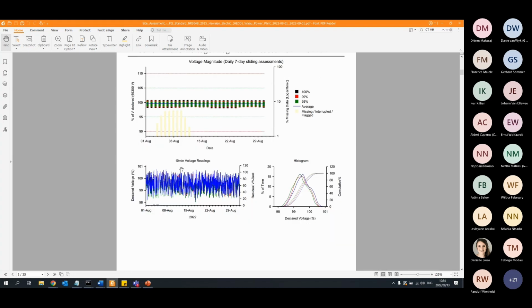So that's all well. If you look at the 10-minute readings, the actual readings and not the sliding assessment, you can see how your three phases change over time. And this is most likely impacted by daily loads that go up and down. If you look at the histogram, we can also see it's well balanced. So your three phases are well balanced. And for most of the time, the highest peak, 15% of the time, it's close to 99.5% of the declared. Right, and you can see that this band from its lowest value to its maximum value is small. So the variation in the voltage is not high. Yes.